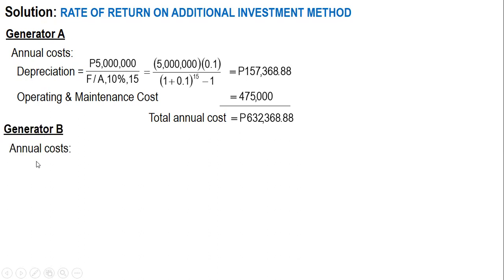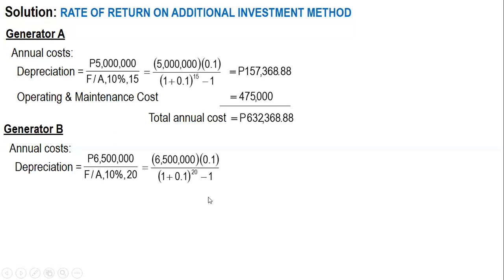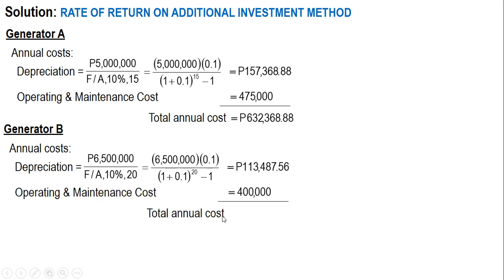For Generator B, depreciation is also computed using the sinking fund method: 6.5 million pesos at 10% over 20 years. Using the formula — first cost times i divided by (1 + i)^n minus 1 — the depreciation is 113,487.56 pesos. Adding the operating and maintenance cost of 400,000 pesos, the total annual cost for Generator B is 513,487.56 pesos.